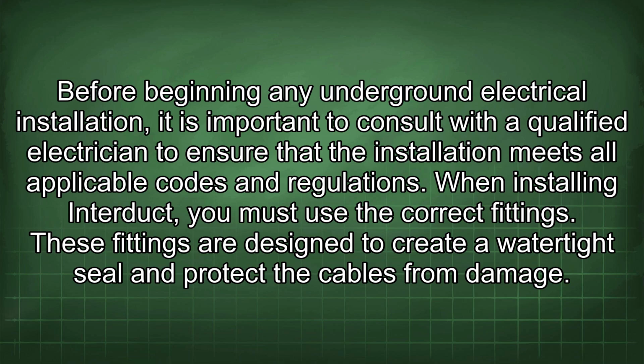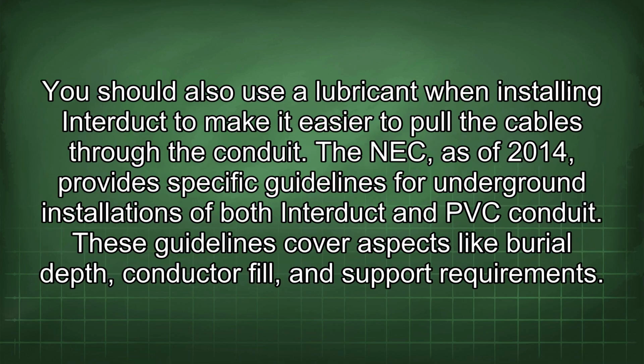Before beginning any underground electrical installation, it is important to consult with a qualified electrician to ensure that the installation meets all applicable codes and regulations. When installing Interduct, you must use the correct fittings. These fittings are designed to create a watertight seal and protect the cables from damage. You should also use a lubricant when installing Interduct to make it easier to pull the cables through the conduit. The NEC, as of 2014, provides specific guidelines for underground installations of both Interduct and PVC conduit. These guidelines cover aspects like burial depth, conductor fill, and support requirements.